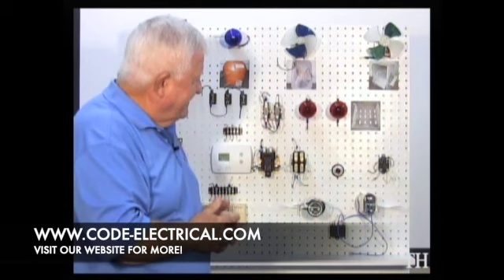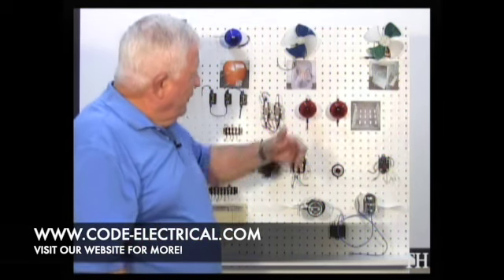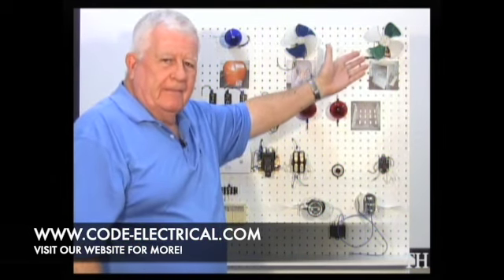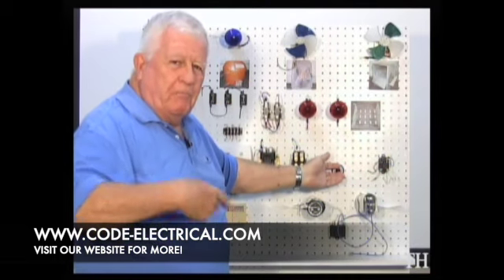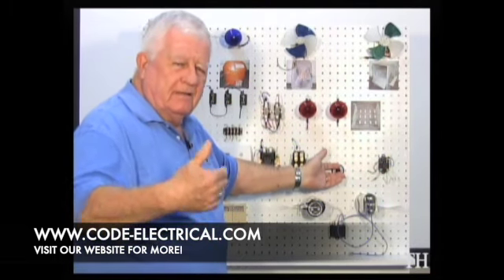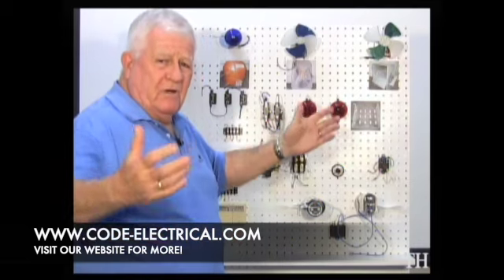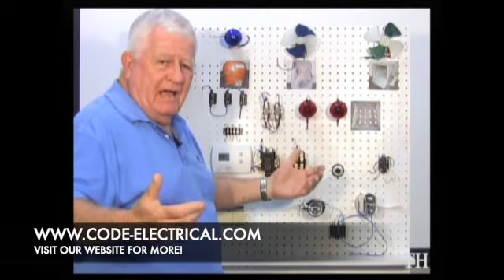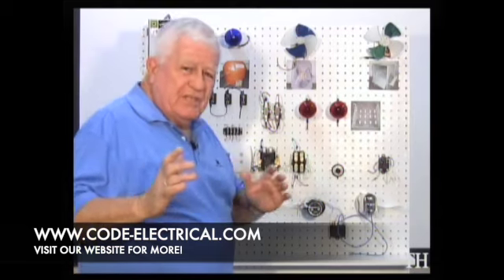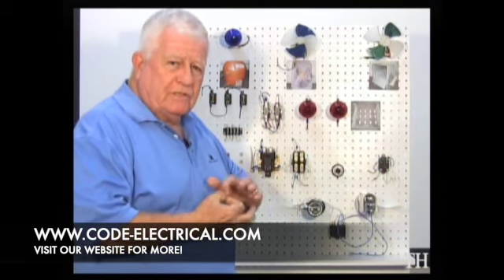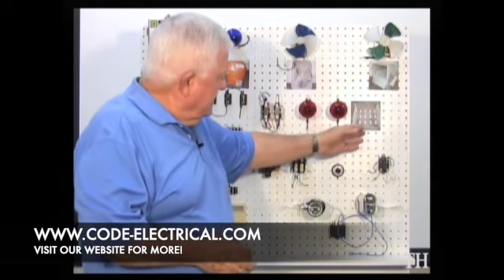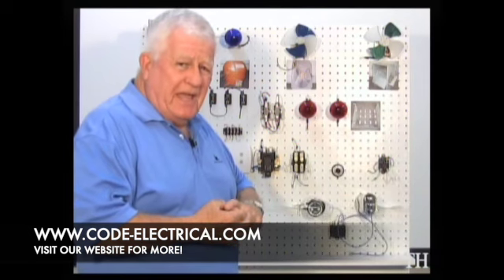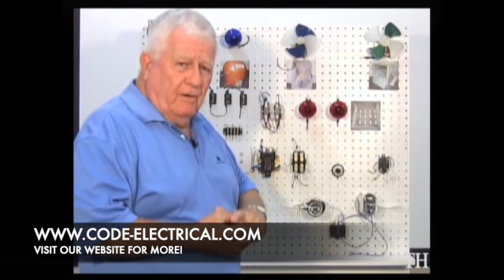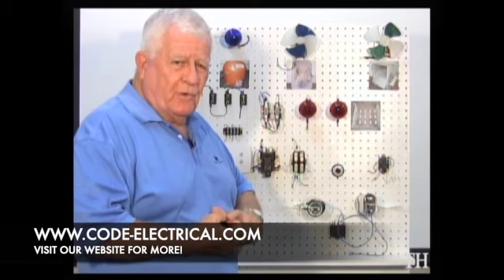Now, some have asked, well, what if the fan didn't come on? What if it just kept burning and burning the gas in the heat exchanger to where it got so hot it melts or ignites the house? Well, you'll see later there's a high heat bonnet. It's like a warp switch, works on temperature. You even have it in the electric heat. You'll see it in that compartment. In case something doesn't happen, it will shut it off to prevent a dangerous situation.